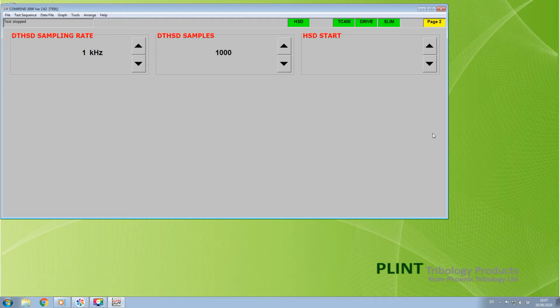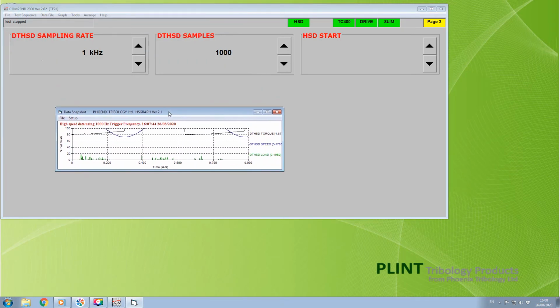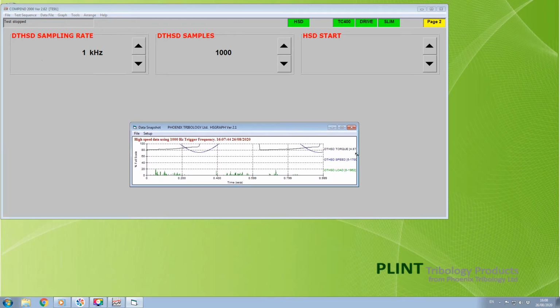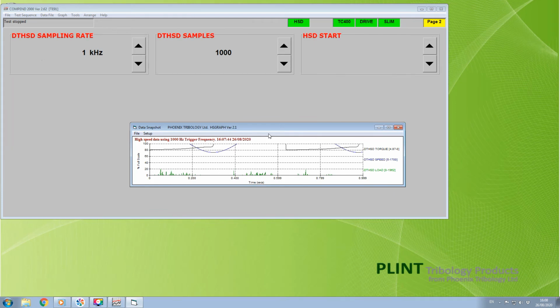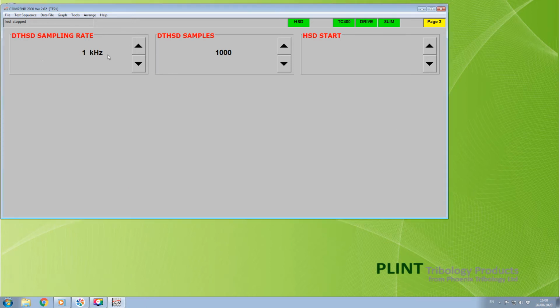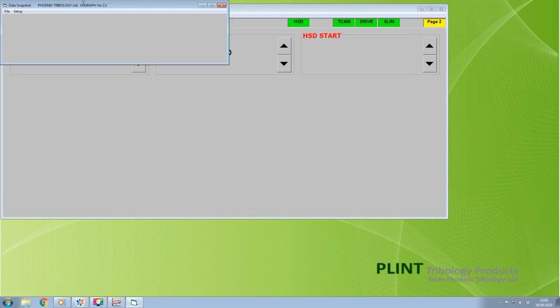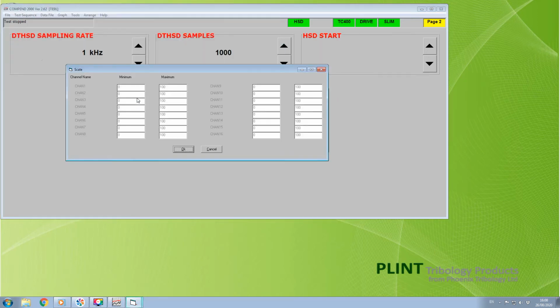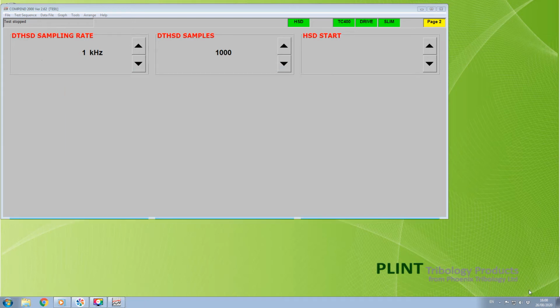This will sample all the inputs physically connected to the high-speed data acquisition interface. The sampled data is displayed in a new graph window. Note that this is overwritten every time that high-speed data is triggered. The window can be repositioned on the screen as required. In much the same way as the low-speed data graph, the high-speed graph can be rescaled by clicking on Edit and amending the values in the table presented.